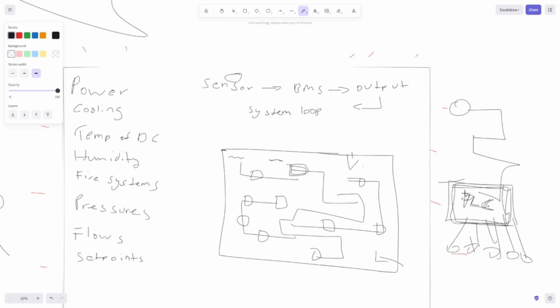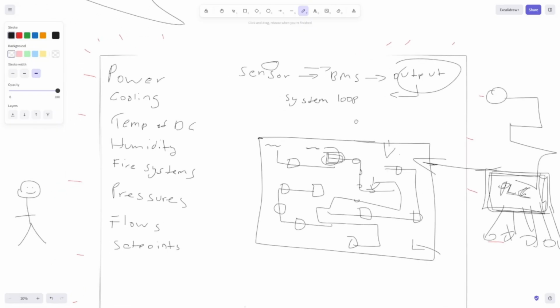And it sends data out into the BMS where it shows you, it has like a UI basically, where it shows you this is my equipment right here, these are the sensors that I have on the equipment, and these are the values that it's showing me. So the sensor out in the field sends data into the BMS, shows you what's going on, and from the BMS you can control what output you want from the data center.